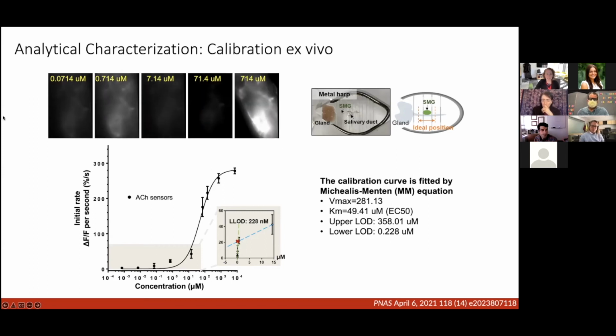And then we can analyze this data, plot the concentration of acetylcholine we added versus the rate of fluorescence intensity, and build a calibration curve. With this calibration curve, we can find the lower limit of detection, the area where we feel comfortable making a measurement, which was 228 nanomolar. We can also use this calibration curve in our next in vivo experiments. So when we're doing our in vivo experiment, if we measure 200, we can use our calibration curve to say that the concentration we measured was whatever the level is.